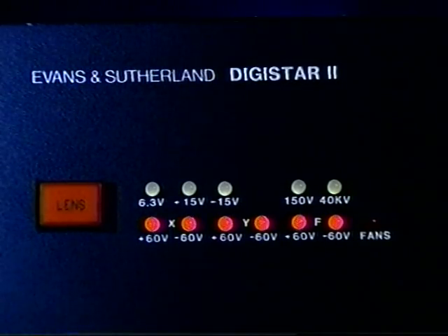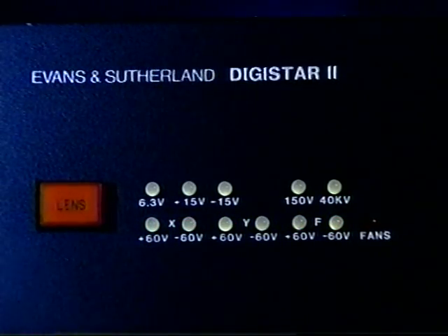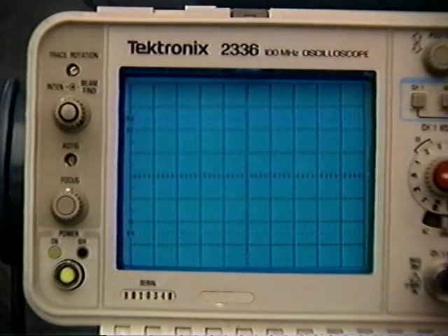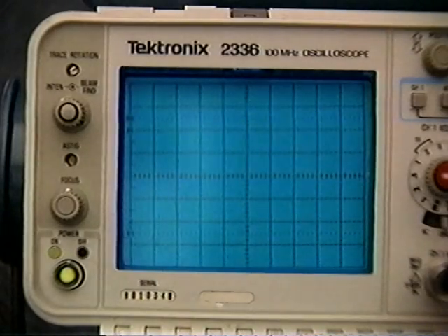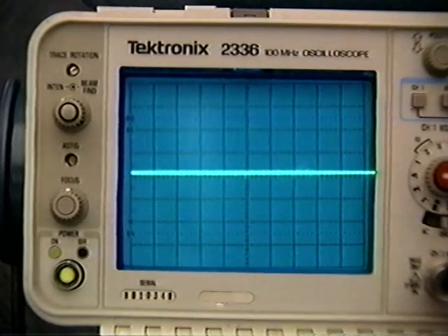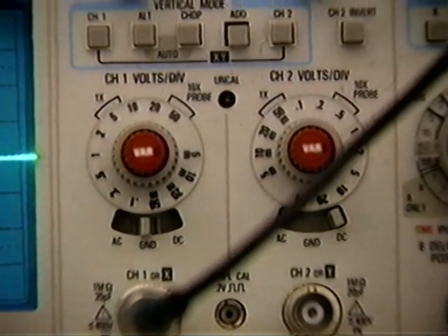All power supply LEDs except fan should eventually turn green. Remember that the sequencer may take up to 8 minutes to finish the power-up cycle. Turn on the oscilloscope and allow it a few minutes to warm up. Ground the scope probe and adjust the vertical centering for 0 volts DC at the bottom of the screen grid.